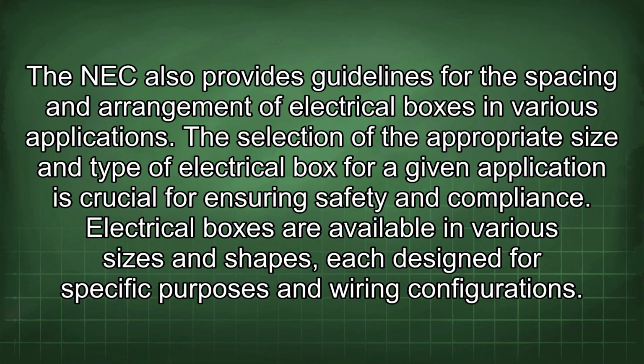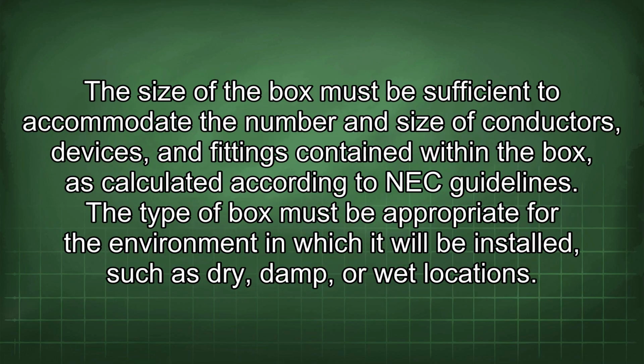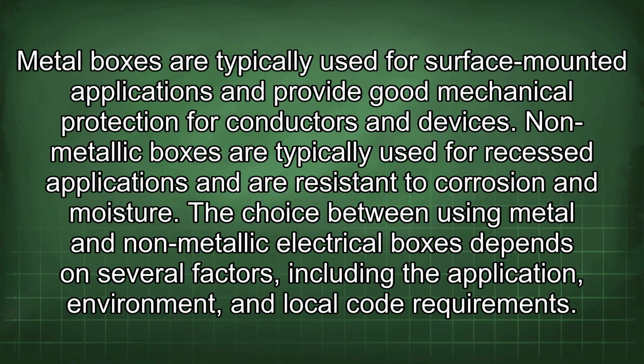and compliance. Electrical boxes are available in various sizes and shapes, each designed for specific purposes and wiring configurations. The size of the box must be sufficient to accommodate the number and size of conductors, devices, and fittings contained within the box, as calculated according to NEC guidelines. The type of box must be appropriate for the environment in which it will be installed, such as dry, damp, or wet locations. Metal boxes are typically used for surface-mounted applications and provide good mechanical protection for conductors and devices. Non-metallic boxes are typically used for recessed applications and are resistant to corrosion and moisture.